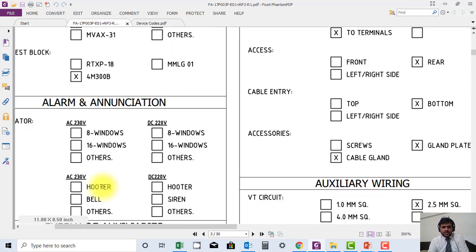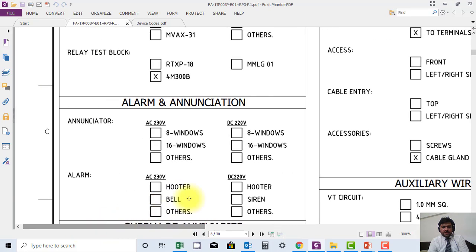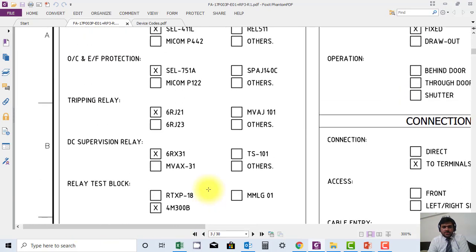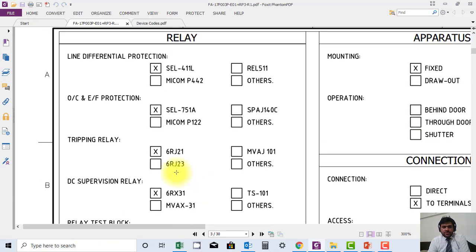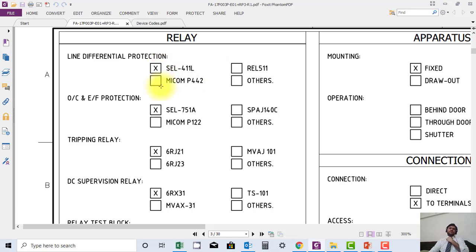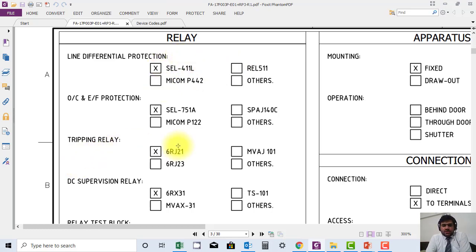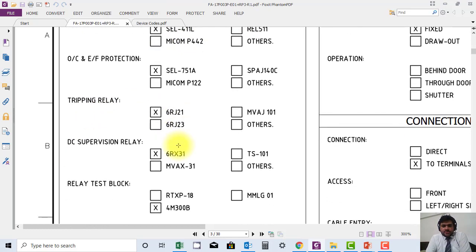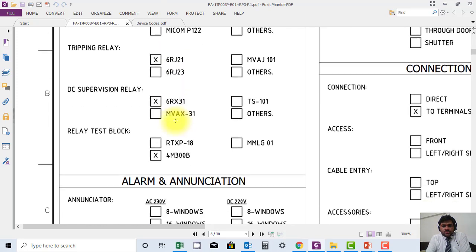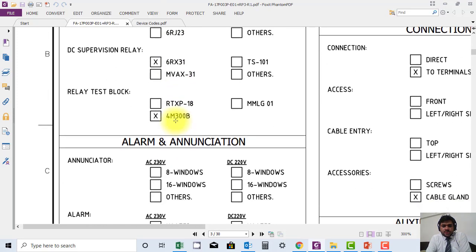We can see here they have mentioned which type of relay is provided. For example, during the bidding document they submitted three options. In this document, the comment was to show all the options and what option is provided. Similarly, they have selected all relays which are used: protection relay, supervision relay, and the relay test block.